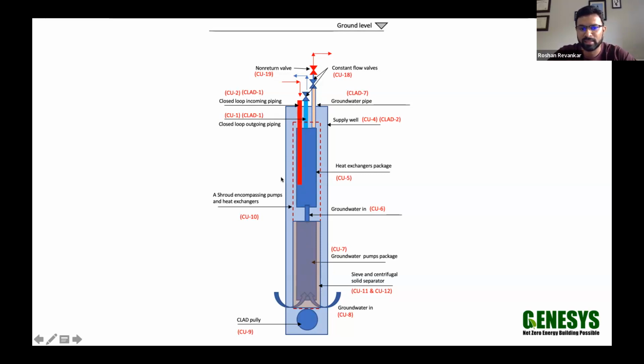What we have at the bottom of this entire CLAD housing is a water well pump. This is nothing proprietary. It's an off-the-shelf water well pump from any of the manufacturers that make these. And it's screwed into the CLAD heat exchanger. So essentially, it's just pushing water through the heat exchanger for activating the heat transfer. The entire CLAD assembly is designed in a way that it can be lowered into a well and removed out of the well, just like how you would install a typical water well pump. And this is the neat advantage of one of these: if this particular pump were to fail, which on average is about 13 years, all you do is pull the CLAD unit out, unscrew the pump, screw in a new one, and drop it back into the same well.